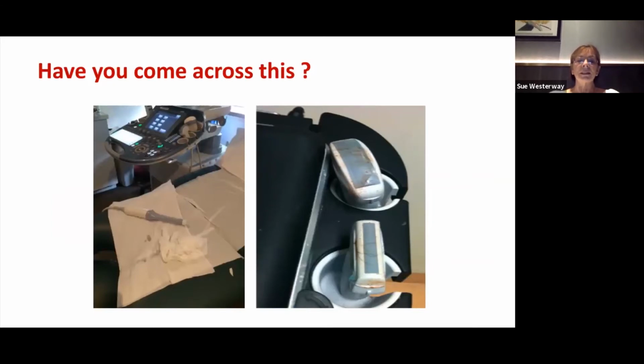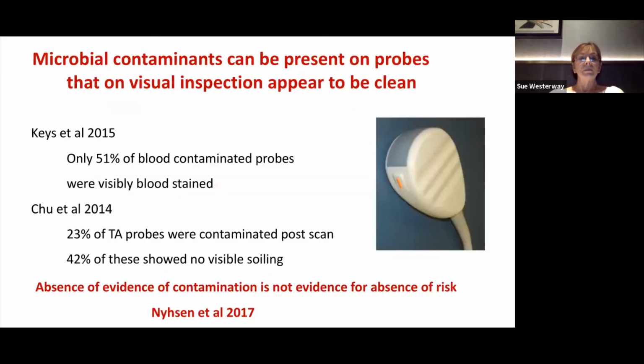How many of you have come across this? You walk into an ultrasound room and the previous user has left blood, gel, hair, and even condoms or probe covers lying around. Microbial contaminants can be present on probes that on visual inspection appear to be clean. A couple of recent studies showed that only 51% of blood-contaminated probes were visibly blood-stained. And in another one, 23% of transabdominal probes were contaminated post-scan, but only 42% of those showed no visible soiling. Absence of evidence of contamination is not evidence for absence of risk.